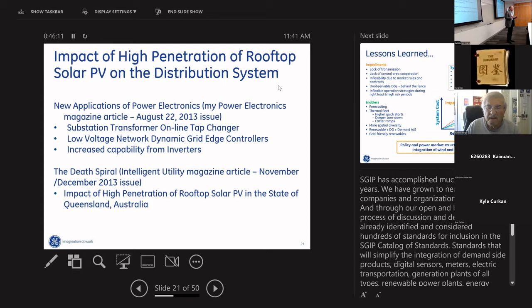The tap changer in the substation is supposed to keep the secondary voltage constant no matter how the primary voltage fluctuates. You want your light bulbs at home to be the same brightness no matter how the voltage fluctuates. Without a tap changer, your bulbs would be very bright, very dim, very bright. So the tap changer is a mechanical controller with 16 raise positions, 16 lower positions, and a neutral position. Each change is 5/8 of a percent of volts.